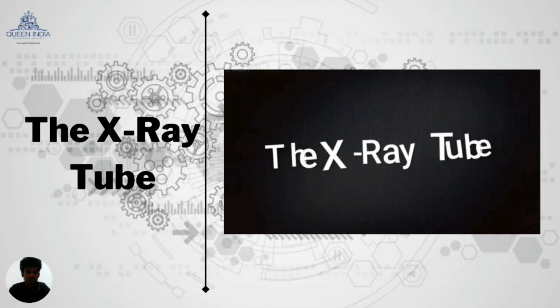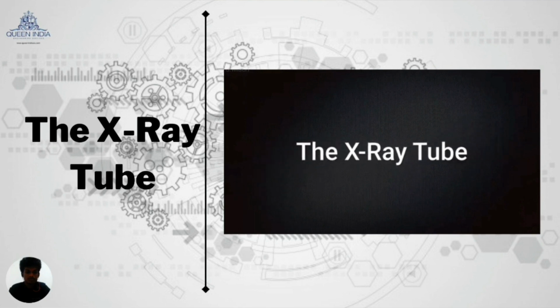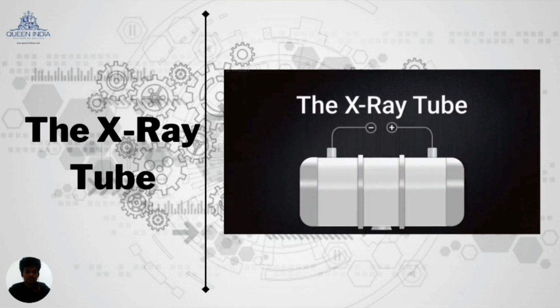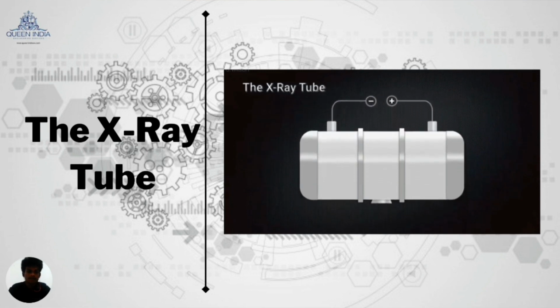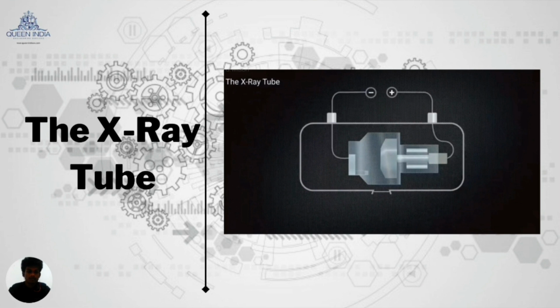First is the X-ray tube. The X-ray tube is the part where X-rays are produced. In the X-ray tube, the electrical input power is converted into X-rays. High voltage supply. The main source of the X-ray is electrons. So to produce higher energy electrons, we have to give higher voltage.